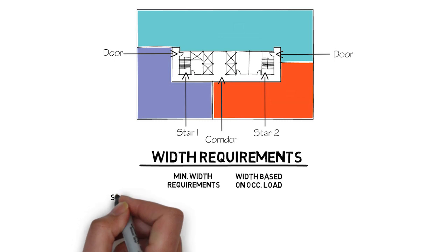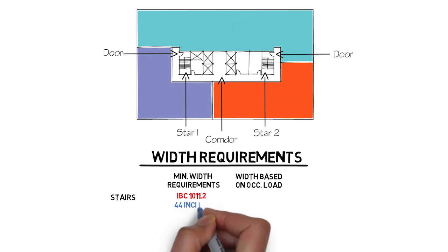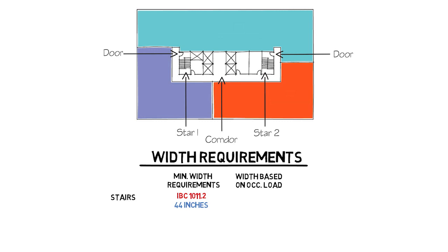Let's start with stairs. First let's look at the minimums required, which can be found in IBC section 1011.2, which notes that the widths must be a minimum of 44 inches. Now let's check the minimum required width based on occupancy load. To provide the answer you will first need the total occupant load for the floor. My last video explains the basics of calculating the width for a suite — a link to that video will be posted at the end of this video and also in the description below.